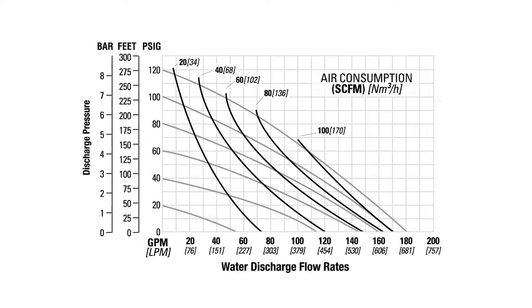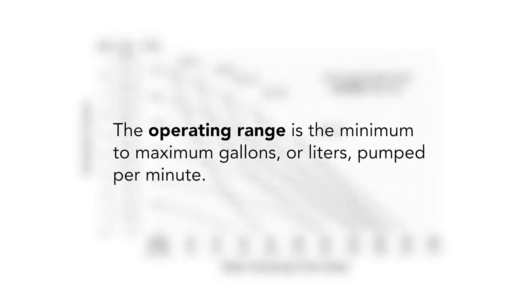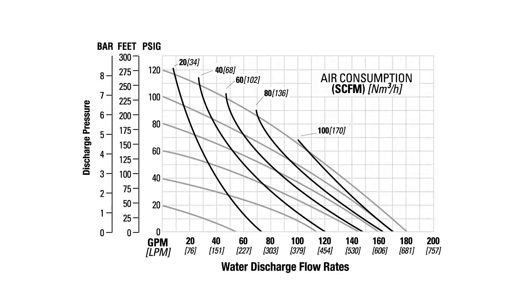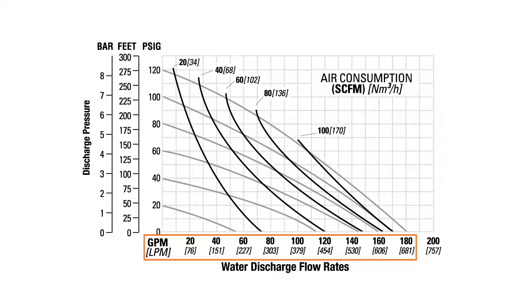The AODD pump's performance curve defines the pump's overall operating range — the minimum to maximum gallons or liters pumped per minute. This is identified by looking at the horizontal axis data range as well as considering the gray air inlet curved axis. For example, this performance curve defines this AODD pump's overall operating range from a minimum of zero gallons per minute to a maximum of over 180 gallons per minute.